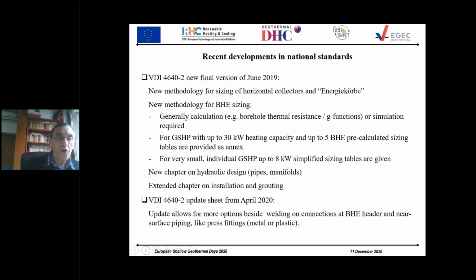The new methodology for borehole heat exchanger sizing deals generally with calculation or simulation. There are some pre-calculated tables for systems up to 30 kilowatts and up to 5 borehole heat exchangers, and for very small individual ground source heat pumps up to 8 kilowatts, simplified sizing tables are given.